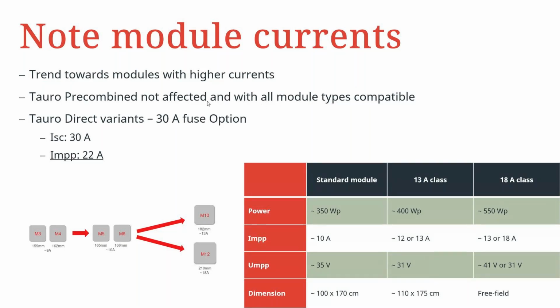In terms of module current, like I've mentioned earlier, we now have a provision that's able to handle higher DC module current capacities. So for cases where your MPP max current is 22 amps, it's recommended you go for the 30 amp fuse. This is because of the evolution of module cells, from M3, M4, M5 up to M12, all having respective current capacities ranging from 9 amps, 10 amps, up to 18 amps module capacities.